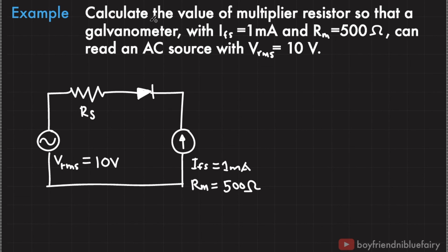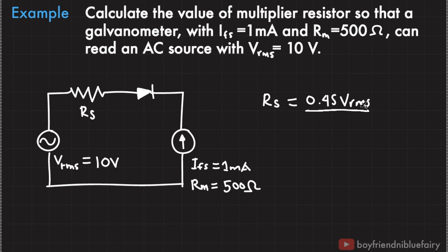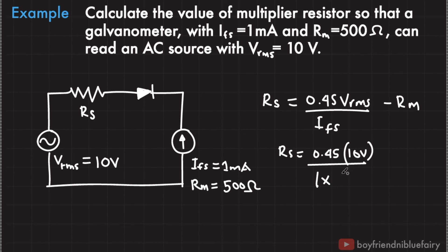As an example: calculate the value of the multiplier resistor so that a galvanometer with full scale deflection current of 1 milliamp and internal resistance of 500 ohms can read an AC source with RMS voltage of 10 volts. Using the equation R sub S equals (0.45 times V RMS divided by I sub FS) minus R sub M: R sub S equals (0.45 times 10 volts divided by 1 milliamp) minus 500 ohms, which results in R sub S equals 4,000 ohms.